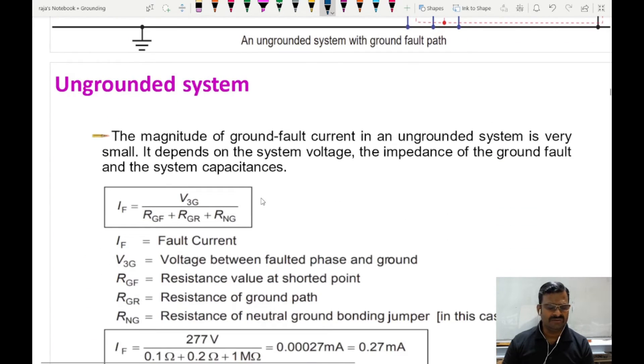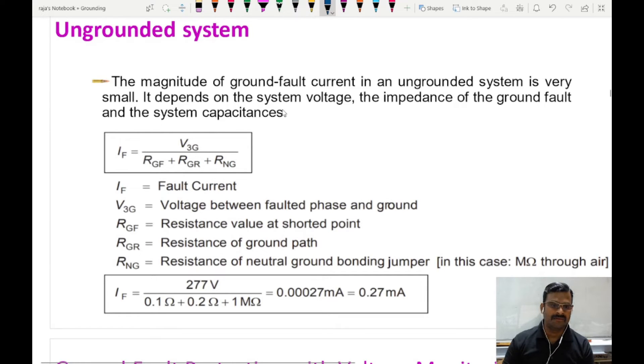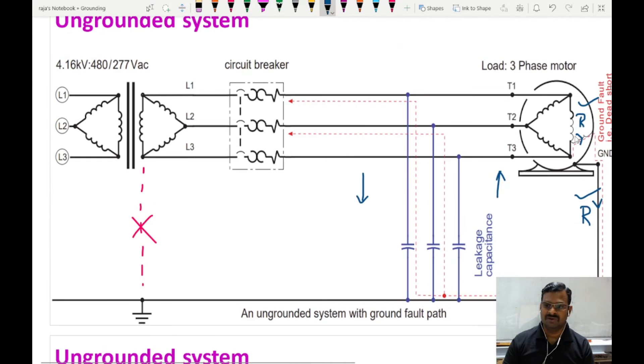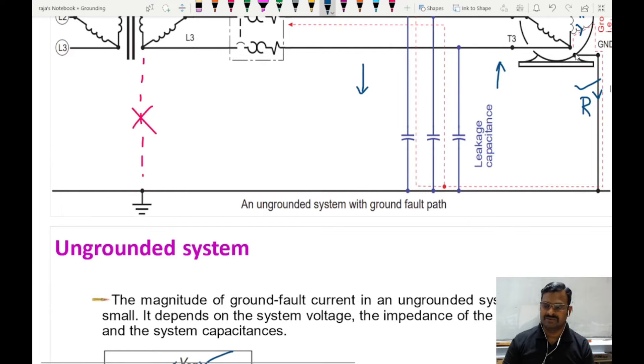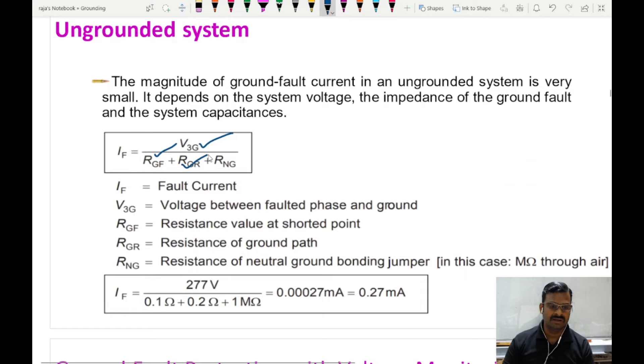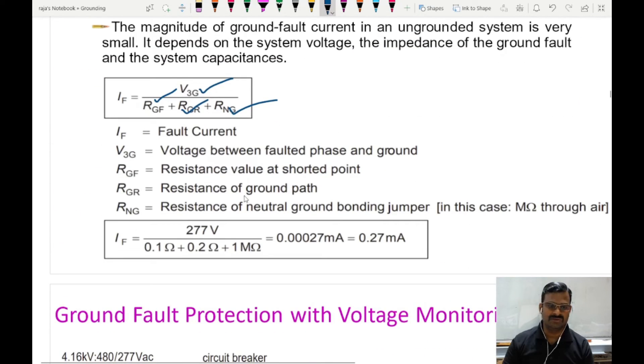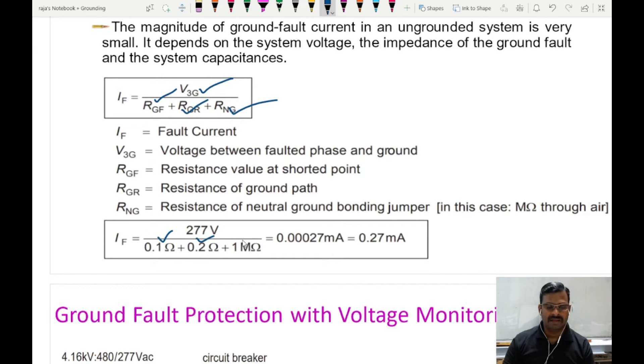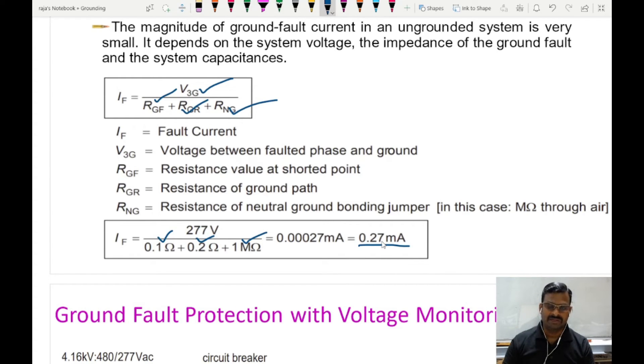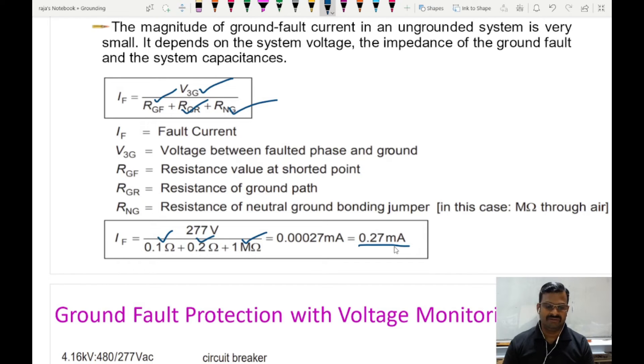Let us see the values. This is the formula used for finding the fault current — phase voltage divided by the total resistance in the path. The resistance of the fault path is 0.1 ohm, the resistance of the conductor between equipment and earth is 0.2 ohm, and the capacitive coupling resistance is 1 mega ohm. The leakage current for this system is only 0.27 milliampere — very small to detect through circuit breakers. We must have special equipment to find out this fault current and rectify the fault.